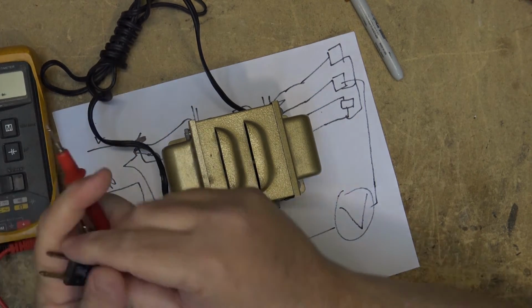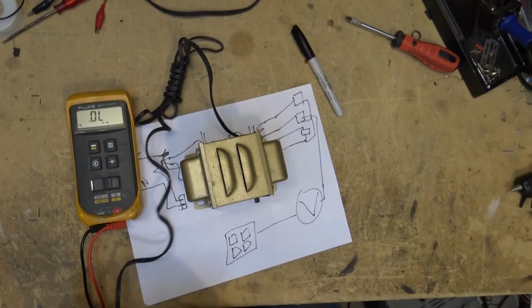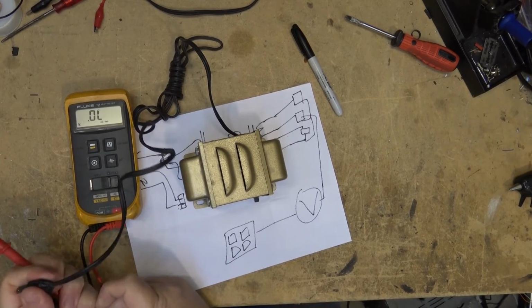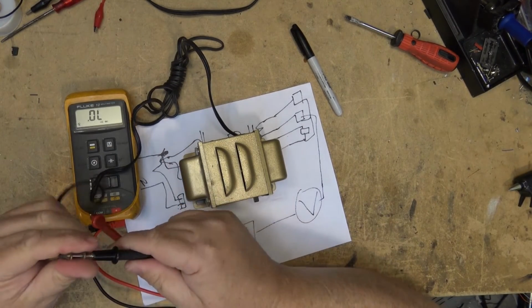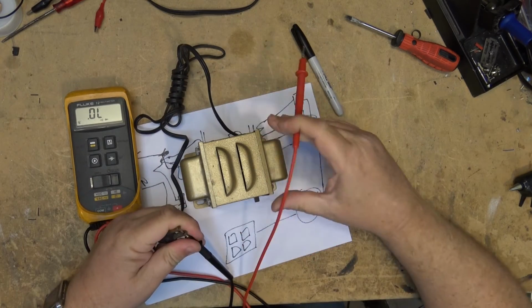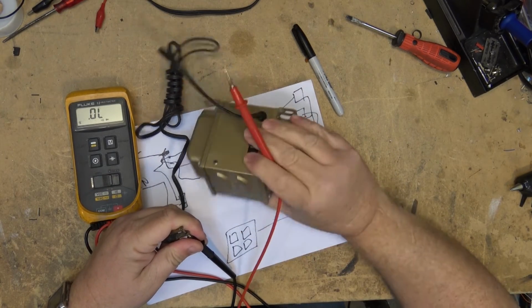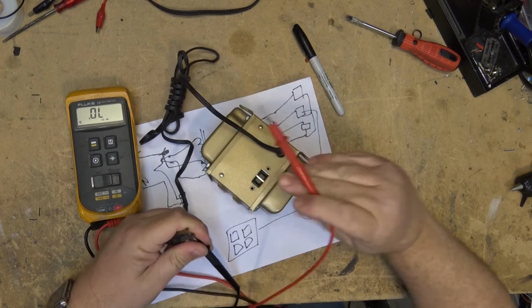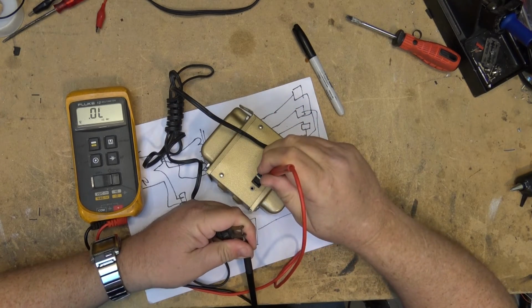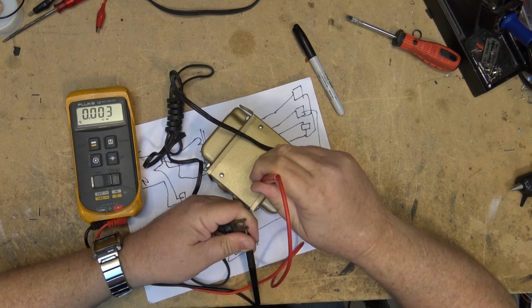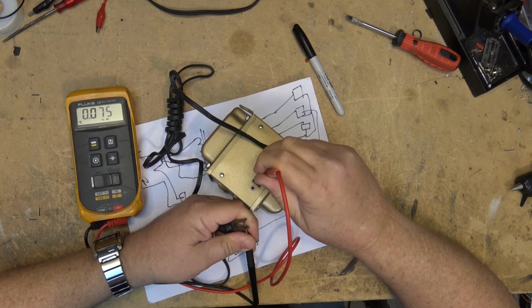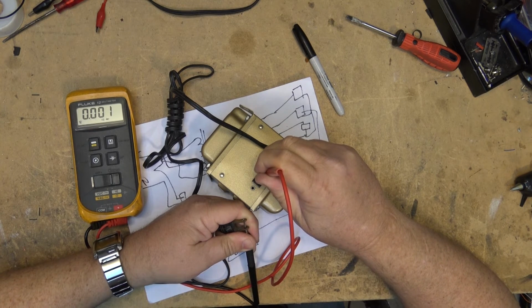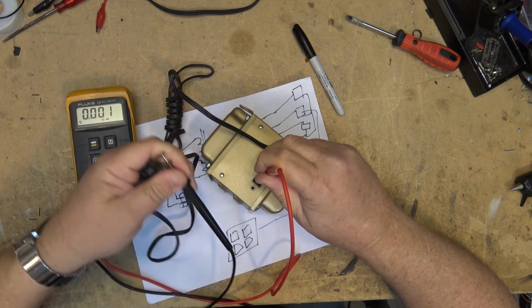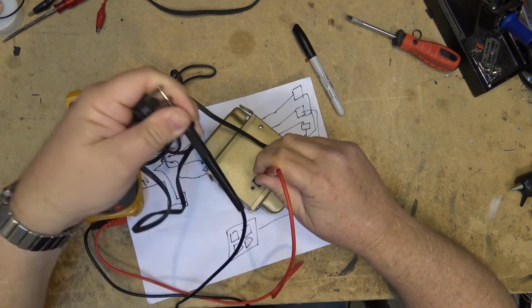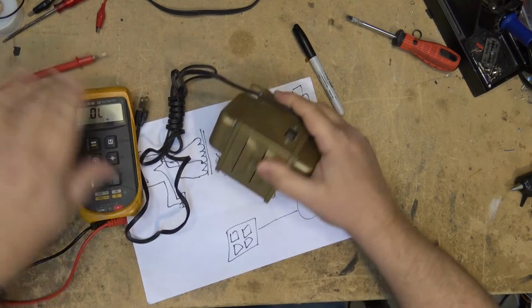Again, as I showed you before, a quick easy way to test it is to take your meter, connect your AC cord to one side, put your probe through and touch both terminals. Make sure it's in one of the on positions, and you should have no resistance. If you get any type of resistance or continuity, that's no good - you're not isolated. We have a direct connection between the input and the output. An isolation transformer won't have that.